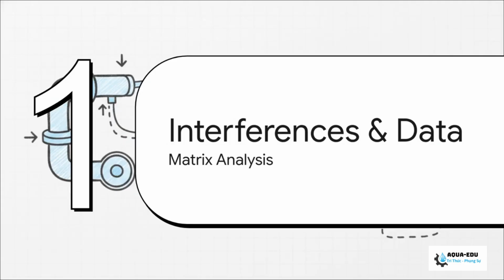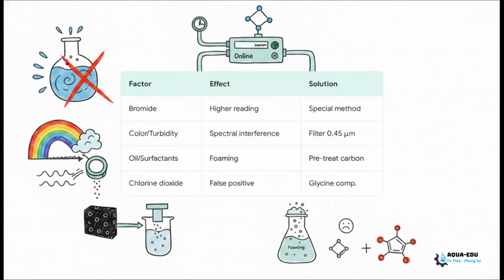Finally, let's wrap up with Section 6, interferences and data mapping. Your sample matrix really matters because false positives are your worst enemy here. Bromide, for instance, will cause artificially high readings because the machine will measure bromine too. Color and turbidity interfere directly with the 510 nanometer spectral light, so if you have high turbidity, you absolutely must use a 0.45 micron filter.